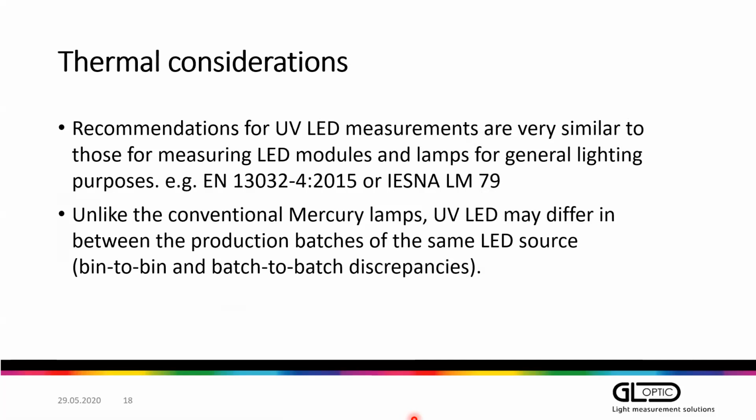So when you are measuring, you can use the guidance on European standard or American standard regarding LED modules, lamps and luminaires, because these standards were prepared primarily for lighting, but also touching the subject of thermal considerations, which is applicable for UV LEDs as well.